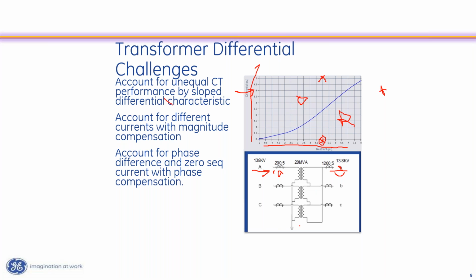Also, if you look at this ground right here, that's a ground source for any fault out in here. So if I had a B phase to ground fault out on my transmission system, let's say this is a generating station and I got a generator right here, that ground right there will pass zero sequence current to that fault. Now, because of that delta to Y transition there, I won't see that zero sequence current on the generator side of this transformer. And that's going to cause me a problem unless I remove that in some way. So not only do I need to do phase compensation, I need to do zero sequence compensation as well. So I've got to do all these things with the transformer protective relay.